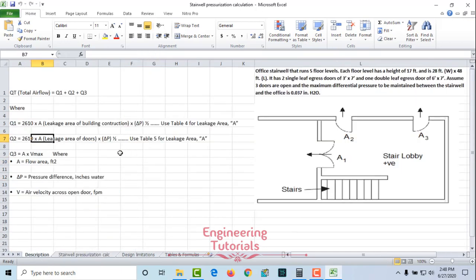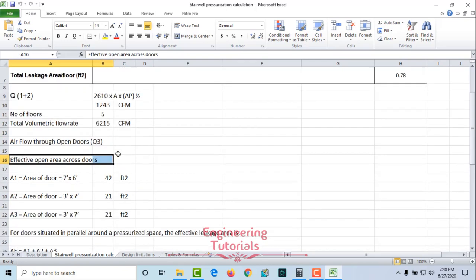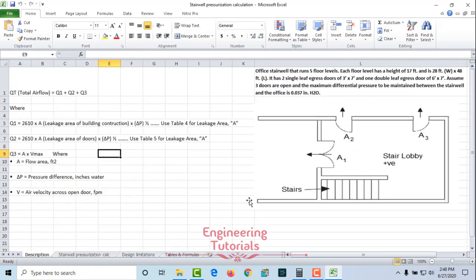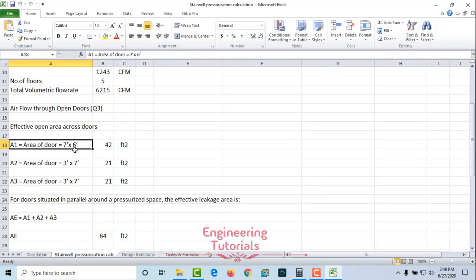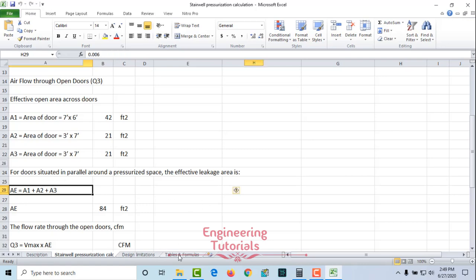Now we calculate Q3. Q3 is given by Q = A × V_max, where A is the effective open door area. We have three doors: A1 is the double-leaf door (7×6 ft = 42 sq ft), and A2 and A3 are single-leaf doors (3×7 ft = 21 sq ft each).